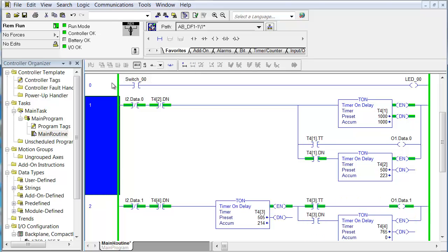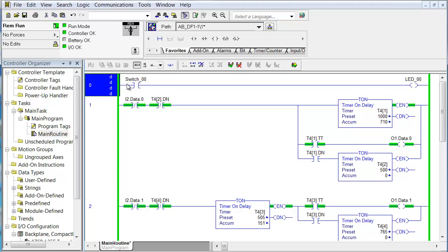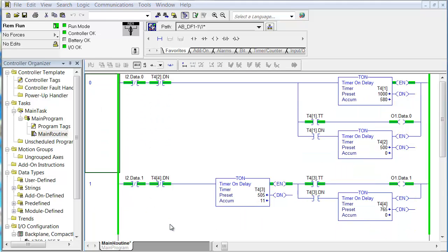This rung I want to delete — we're not really using it anymore. So I select it and I could right click or just hit the delete key. Hitting the delete key for a rung is not really an edit because we're just getting rid of it. There's a D in front of it for delete. We go to the finalize all edits button, answer yes to the message, and that rung is gone. Now we just have our two timers from the last lab.